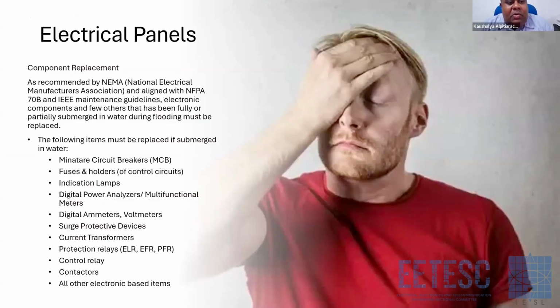Electrical panels, the component replacement. MCBs you can't use. You will have to replace them if fully or partially submerged. If you have seen an MCB, so many rivets are there. You hardly see any sort of screws apart at terminal points. So it is hard to dismantle and refix. Therefore, the drying process and cleaning process is very difficult, and it's not pricey as well. You will have to replace.